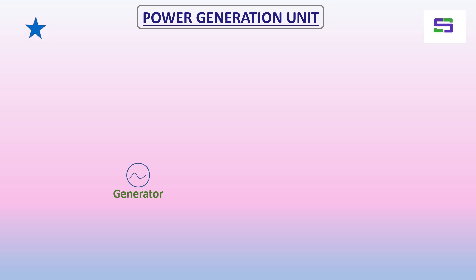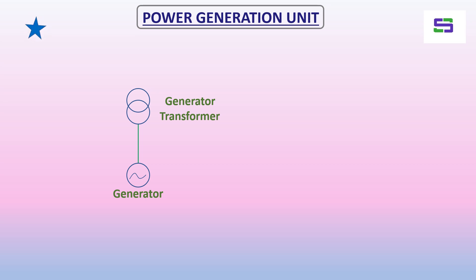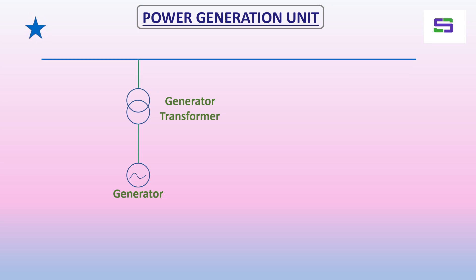There will be one or more generator units and a generator transformer. The generator will generate power at a certain voltage level — maybe 11 kV or 22 kV. This voltage needs to be stepped up to EHV level, that means 132 kV, 220 kV, or 400 kV, to evacuate the power towards the power grid.